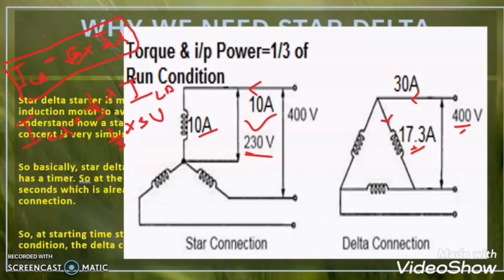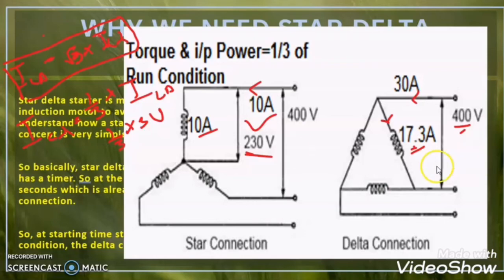So what is the trick? The star delta starter first makes the motor winding in the star configuration. By doing so, the current in the winding and the voltage across the winding will be less, so the starting inrush current will also be less. Once the motor catches its rated speed, the star delta starter changes the motor winding configuration into delta connection to get its rated voltage and rated current.